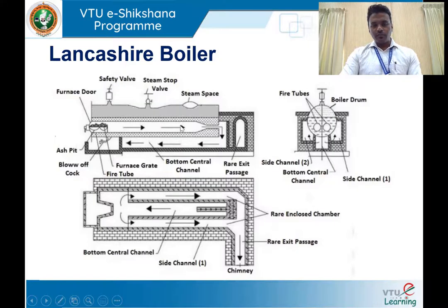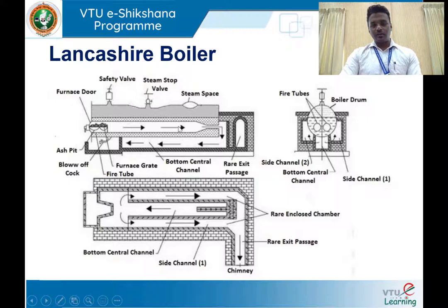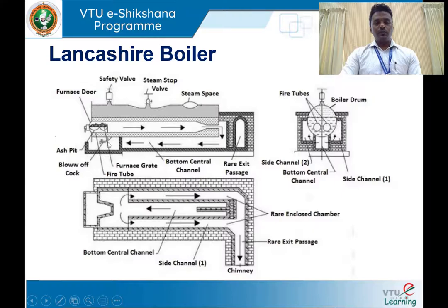One important observation: the flue tube, which has a circular cross-section, changes its cross-section nearer to the rear end to a conical section. The main reason is to increase the velocity of flue gases at the rear end of the boiler shell. The fuel burning takes place in the furnace. Since the Lancashire boiler is an internally fired type, the furnace is placed at one end of the flue tube — it is a part of the boiler shell.